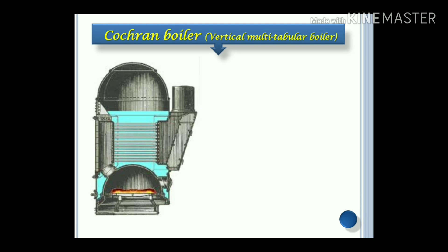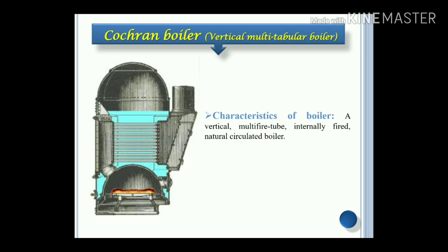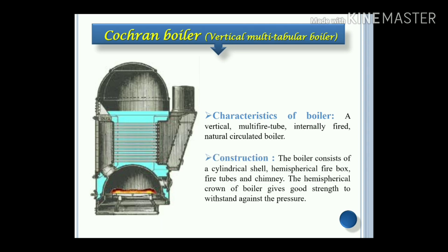Let's see the figure of the Cochran boiler. As per the classification of the boiler, according to the geometric orientation, it will be a vertical tube boiler, multi-fire tube boiler, internal fired and natural circulation kind of boiler. The boiler consists of a cylindrical shell, hemispherical firebox, fire tubes and chimney.